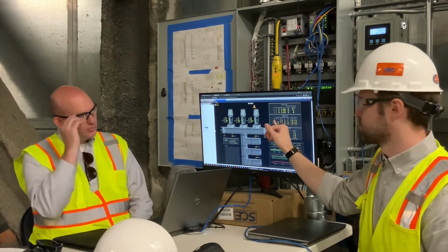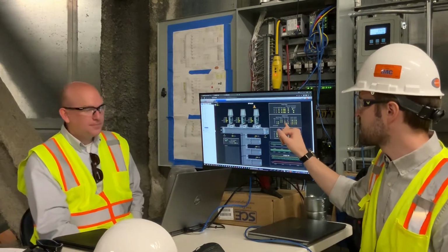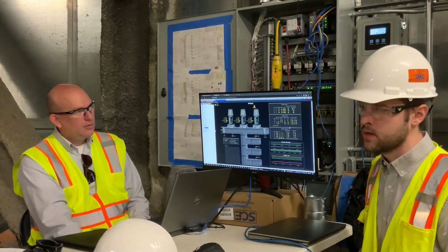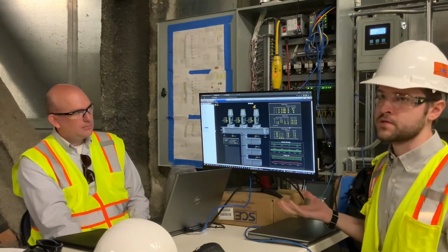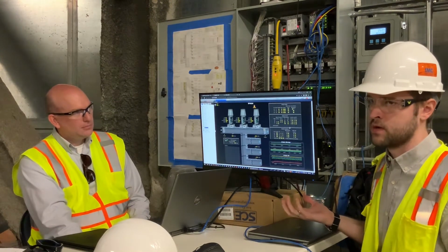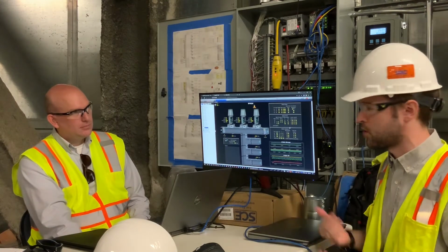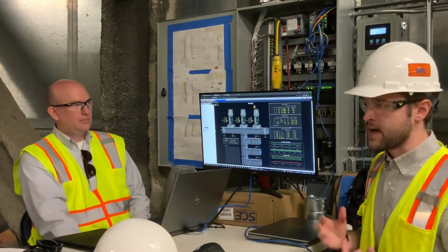There's some built-in delays to bringing on these different stages. These middle two columns here are the parameters that determine the extra stages coming on. So right now, stage 1 should always be on. The parameter that determines whether that comes on is if fan speed is greater than -1. It's always going to be greater than -1, so it's always on. Stage 2 is the only one we ever expect to come on and off.